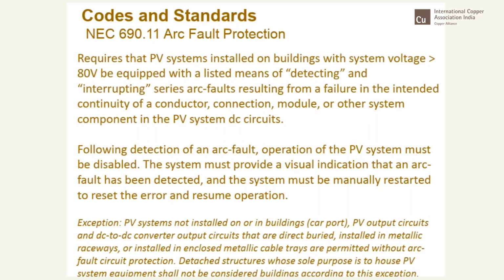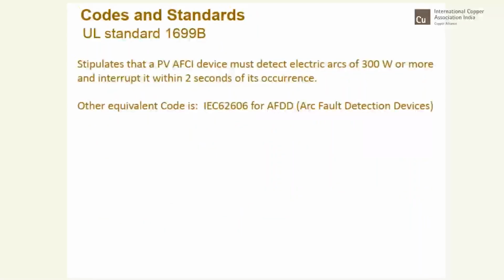prevent this. Now, of course, there are exceptions, because it says PV systems not installed on or in buildings, like in a carport. There is nothing below that, only a car, of course. I really do not understand the logic, but it says this need not be done. After all, there are hundreds in a very big parking lot. I do not know, there should be some logic. Anyway, PV output circuits and DC to DC converter output circuits that are directly buried or installed in metallic raceways or enclosed metallic cable trays are permitted without arc fault circuit detection. You can go through the rest of it, and let us move on to the next slide. It stipulates this code, and the UL also has its own standard.